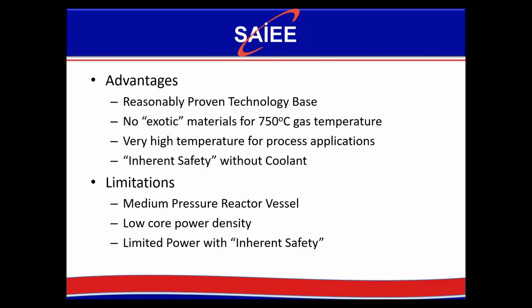As long as you get the gas temperature below about 700 degrees centigrade, there's no exotic materials required. I mentioned earlier that if you're going to build a pressure vessel, if you're going to build an intermediate loop, then you need to have a heat exchanger with helium on one side at your gas temperature and your coolant on the other side, molten salt, steam, whatever it is. And up to about 750, that's pretty much doable. There's no great debate. We can do that. That's very similar to a coal-fired station in many ways in terms of the upper end of the temperatures. It can be done. Clearly, if you get beyond that, you get exotic, and that's where you end up looking at, well, where you've got higher temperatures, you can talk about going for a direct cycle because your temperature drop occurs across the gas turbine, not across the pressure boundary. And the gas turbine hasn't got a safety issue.